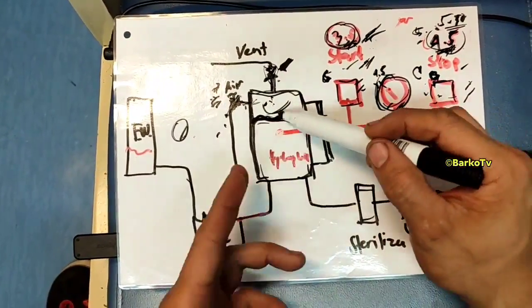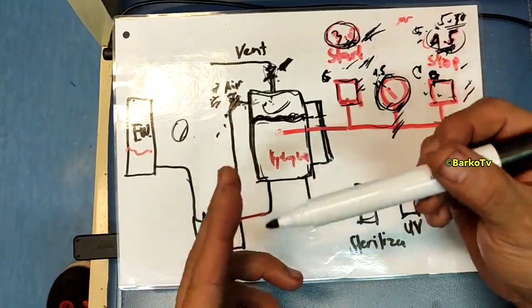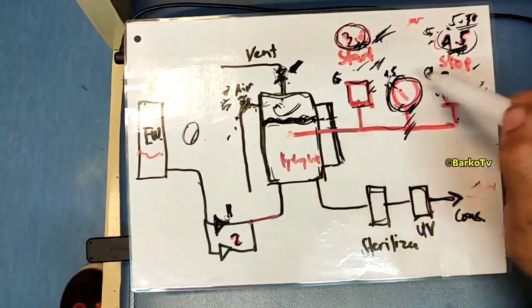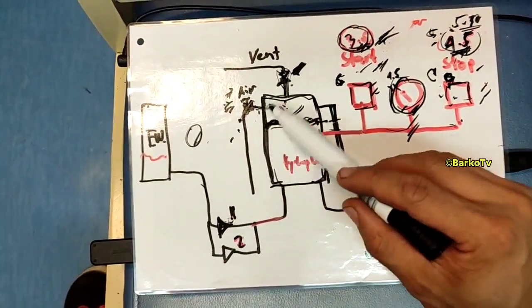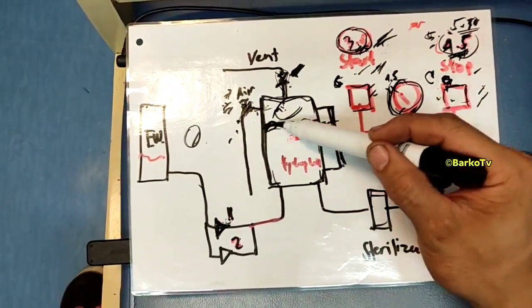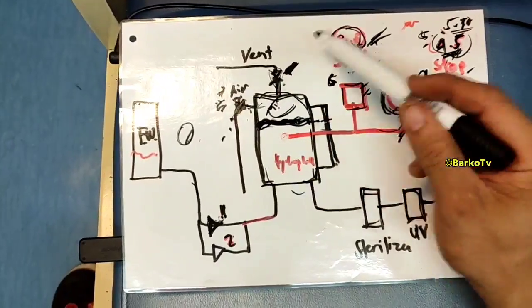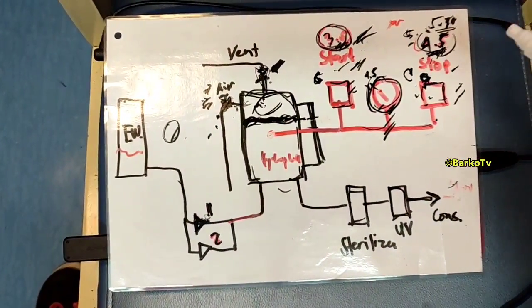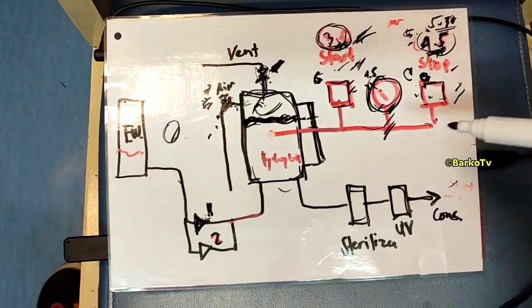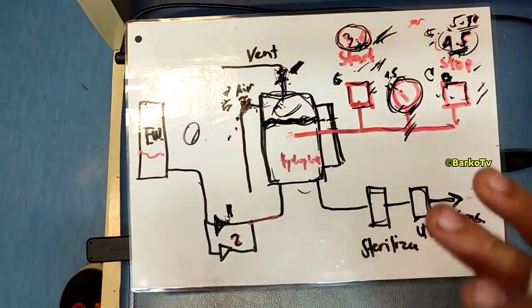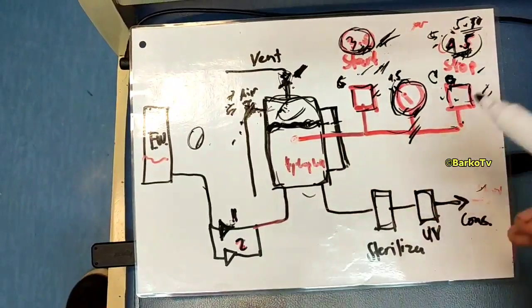After setting, follow the proper procedure: maintain three-quarters water without pressure, then charge air up to 4.5 bar so the hydrophore maintains three-quarters water level. That is the simulation method I used, and it worked for me easily.